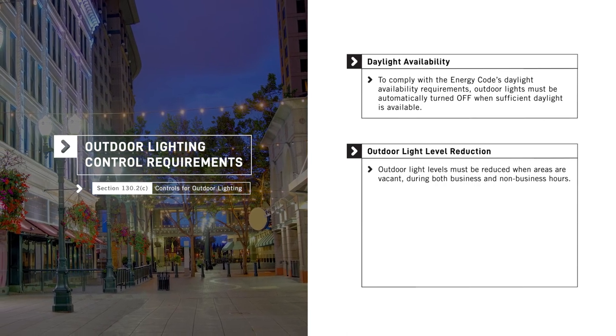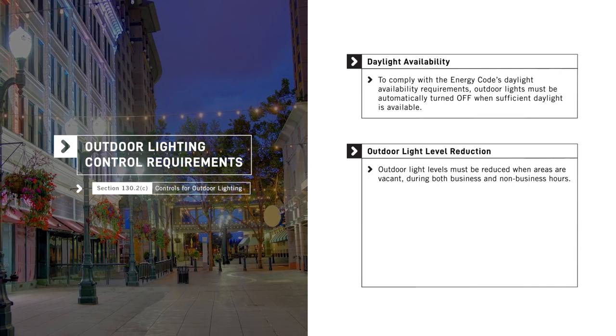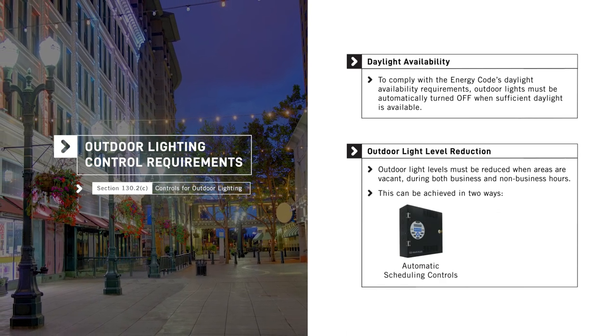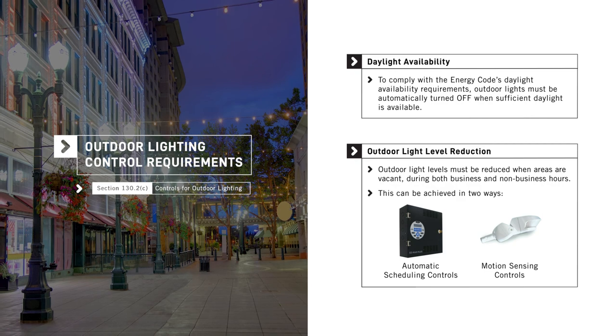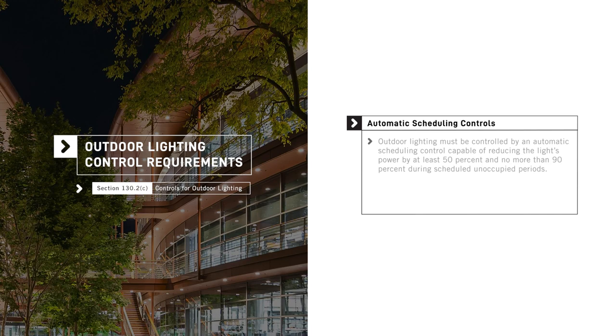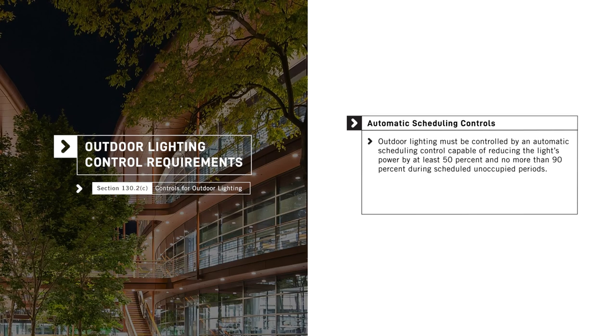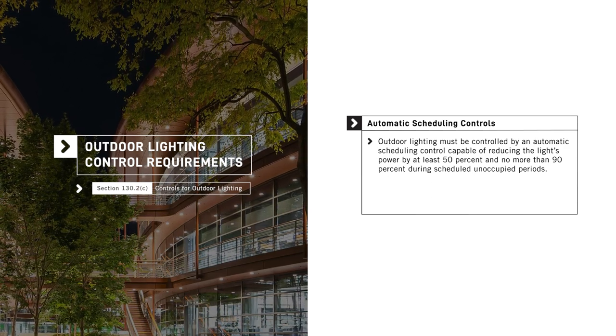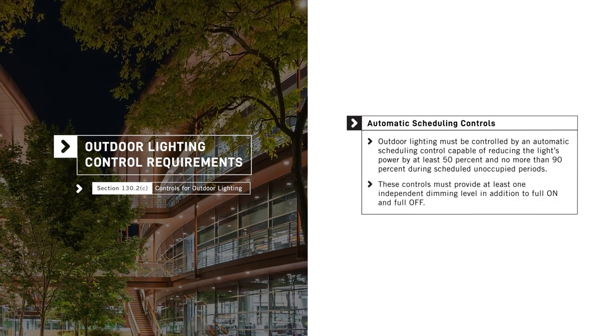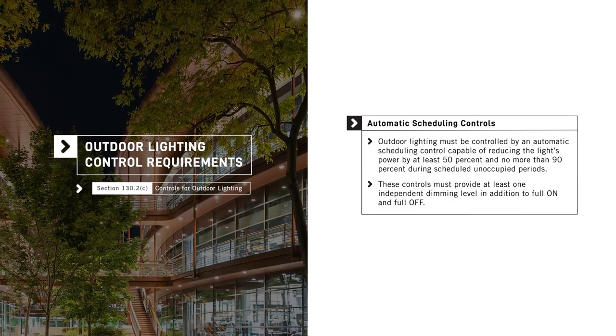The Energy Code also requires that outdoor light levels be reduced when areas are vacant during both business and non-business hours. This is achieved two ways: one, automatic scheduling controls, and two, motion sensing controls. All outdoor lighting must be controlled by an automatic scheduling control capable of reducing the light's power by at least 50 and no more than 90 percent during scheduled unoccupied periods. These automatic scheduling controls must provide at least one independent dimming level, in addition to full-on and full-off.